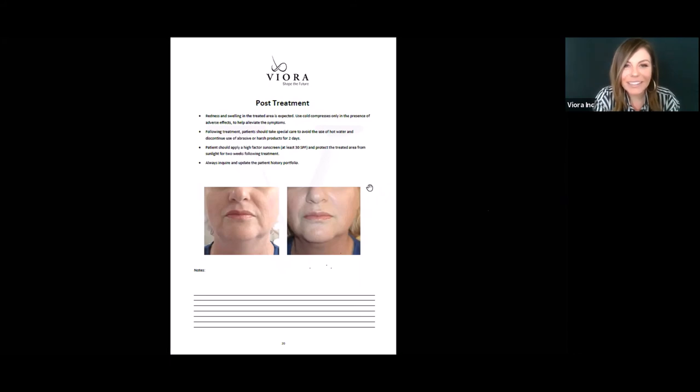You're welcome. In my experience, some people can't stand more than 45 joules, me included. Okay, so I just got a message that they cannot withstand more than 45 joules.